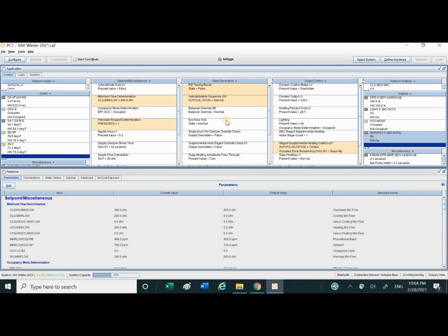We see the off cycle. We use something to cover the occupancy sensor again, so it doesn't sense the people in the zone. It should become unoccupied. And then the output occupancy mode should be unoccupied. And then the lights should be off. So now we cover it back. And also we set the set point lower than the zone temperature. We use the thermostat to set the set point lower than zone temperature. Then the heating should be off.